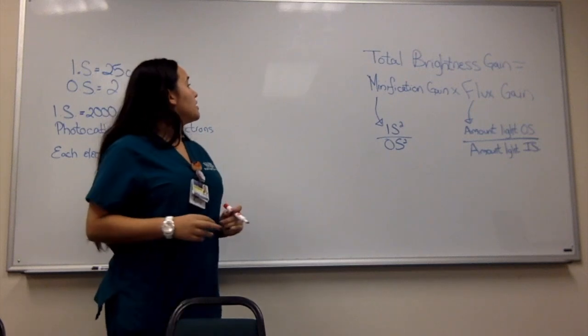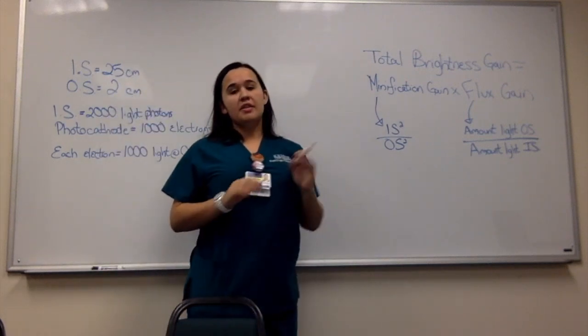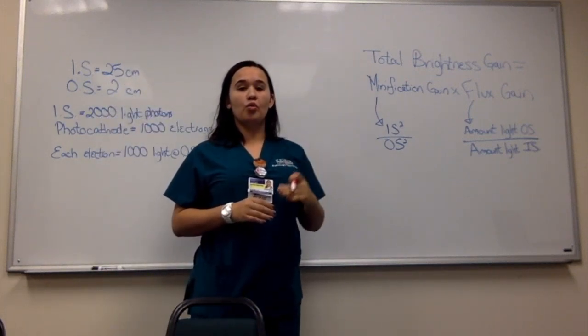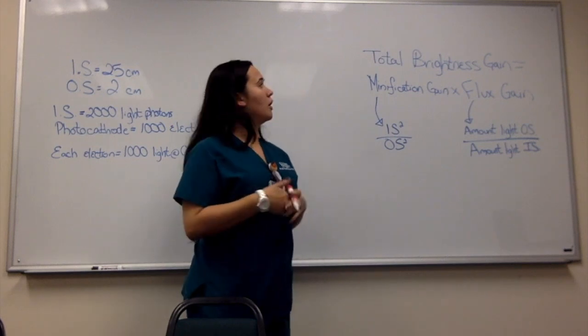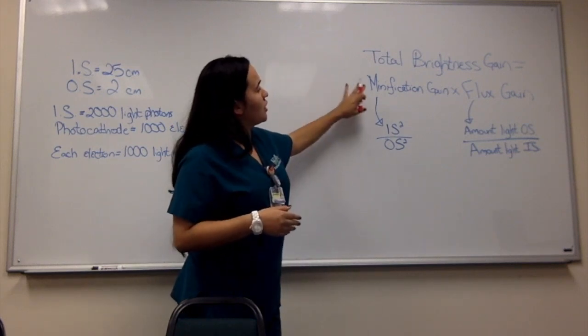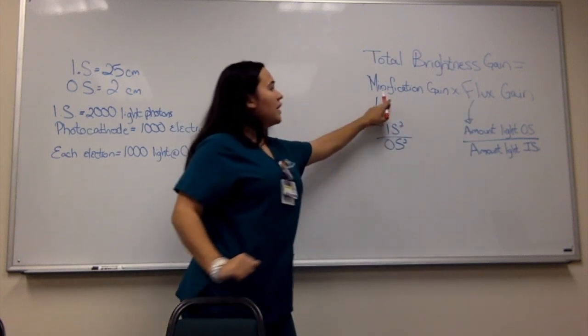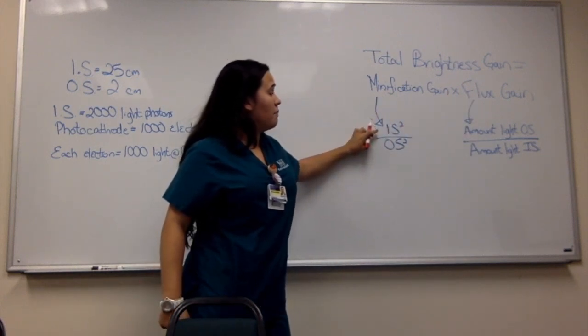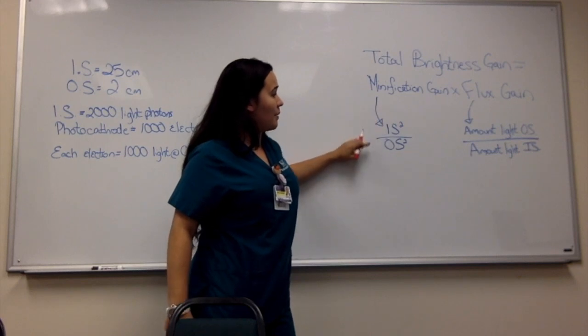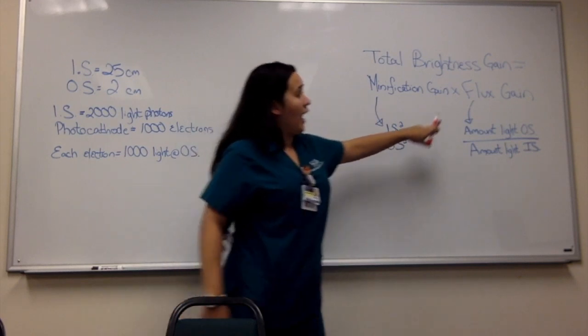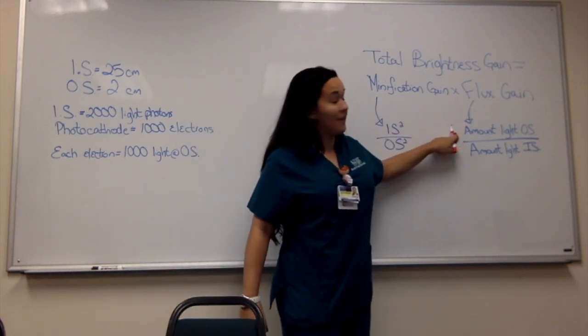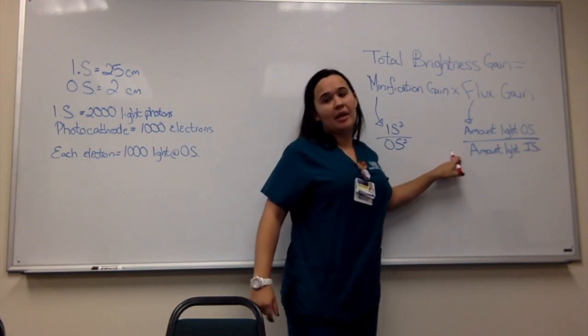So there's also a formula to figure out the total brightness gain. This is how much the intensifying tube makes the image brighter. In order to find that, you need to find the minification gain multiplied by the flux gain. So the minification gain is the input screen size squared divided by the output screen size squared. And the flux gain is the amount of light at the output screen divided by the amount of light at the input screen.